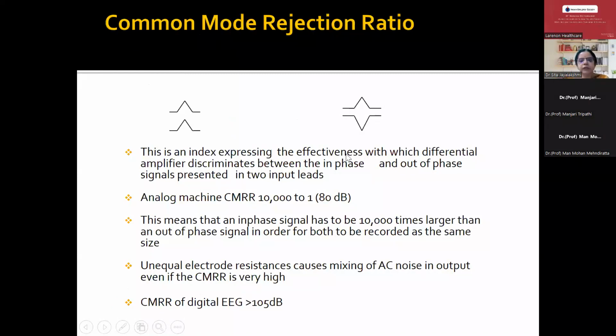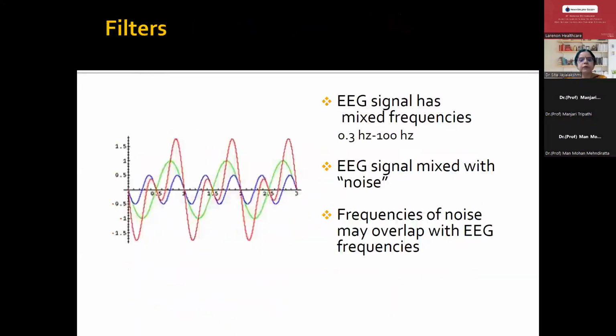It is nothing but the effectiveness with which this differential amplification occurs, and how the machine or amplifier discriminates between the in-phase and the out-of-phase signals presented in the two input leads. This is very important when somebody is using an EEG machine. It is called CMRR. It should be at least 80 decibels. Nowadays, we get machines which are more than 100 decibels, so the common mode rejection ratio of a digital EEG is usually more than 105. It is the ability to discriminate between in-phase and out-of-phase signals.